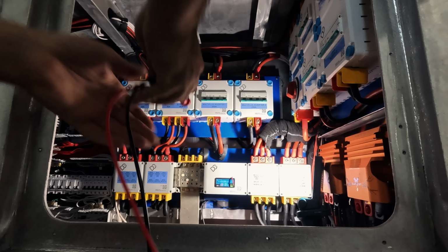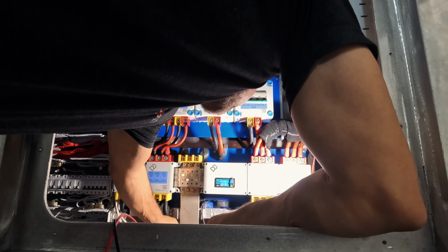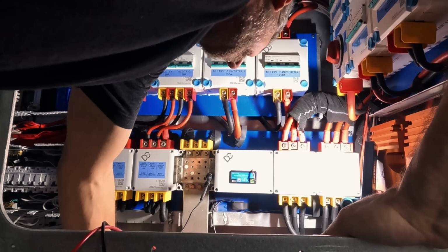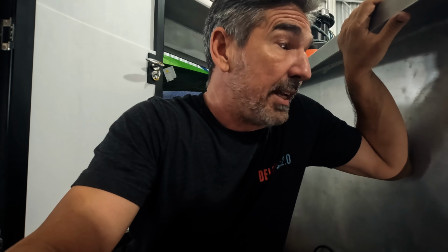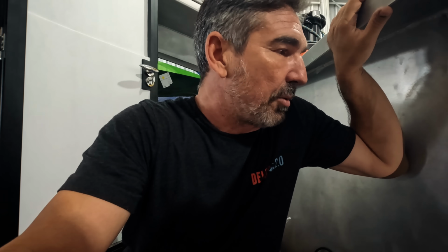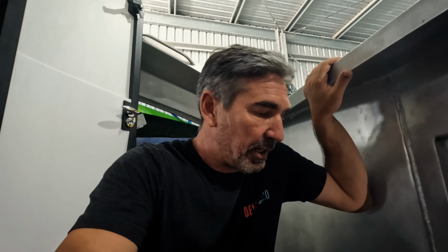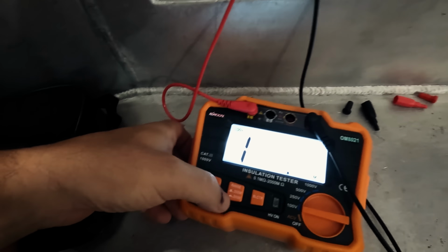I'm going to hook it up to the bus bar inside, positive side, and then pick up the negative side here. I made sure all equipment was unplugged from the bus bar, including the Victron Smart Shunt, because it's not rated for the high voltage we're testing, and I wouldn't want to damage any of it. We're going to be on the 1000 volt setting.